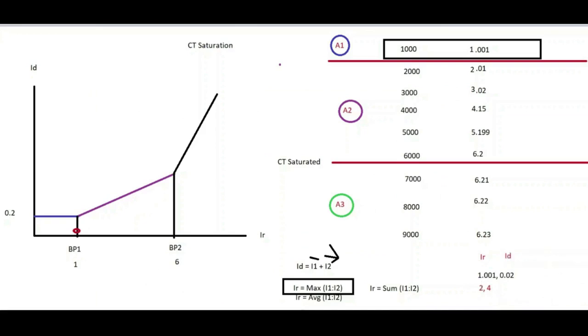So let me write it again. My restraint current is 2 amps maximum. And what is my differential current? 2 plus 2, 4 amps. So plot 2 and 4. 2 somewhere here, 4 somewhere here. Relay will trip because it is plotted above the curve.